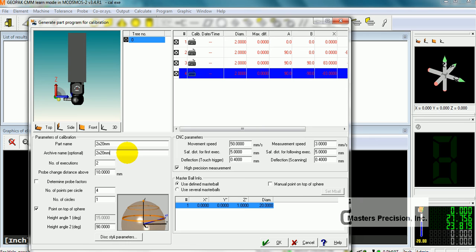Okay. Number of executions 2. I'm going to change it to 1. That's how many times it's going to run it. Probe change distance above is 10 millimeters, meaning it's going to go above the master ball 10 millimeters to change the probe. Number of points per circle is 4. In this particular case, it's going to measure 1 point on top and 4 points around the equator. I can change the angles at which I do that here, and there is disc stylus parameters.